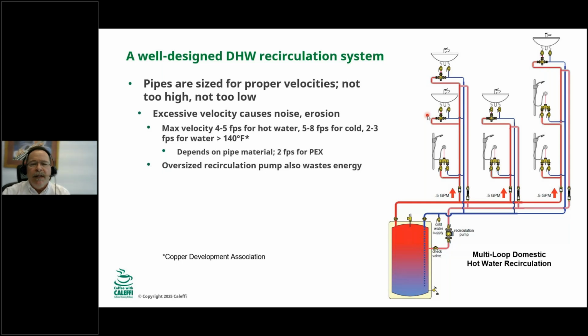So an oversized recirculation pump will also waste electricity. It'll waste energy. We're going to talk about sizing the pump here in a minute, but if your pump is too big, you're going to have too much velocity and cause the problems we just talked about.